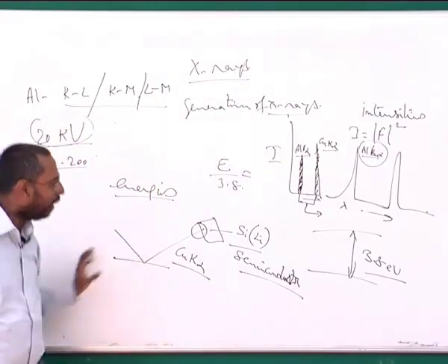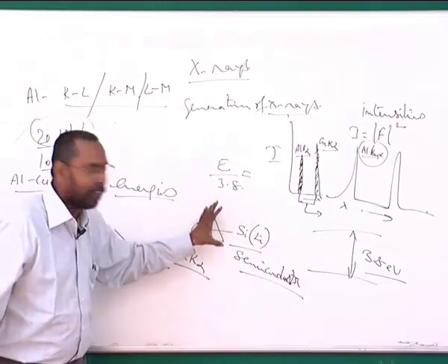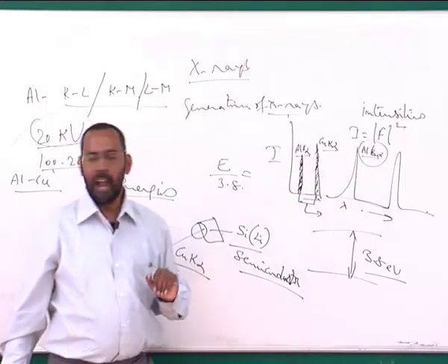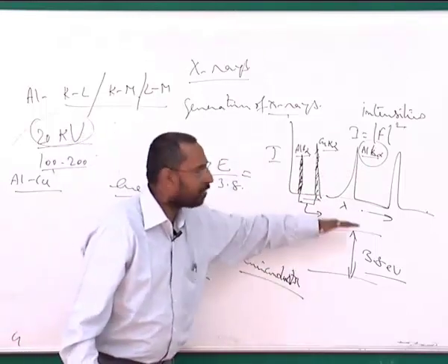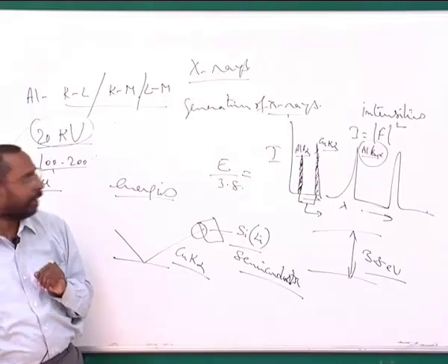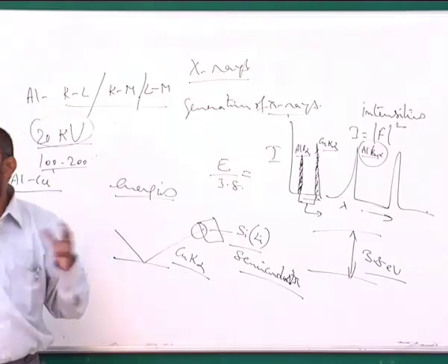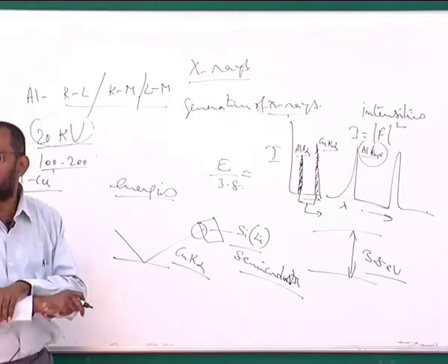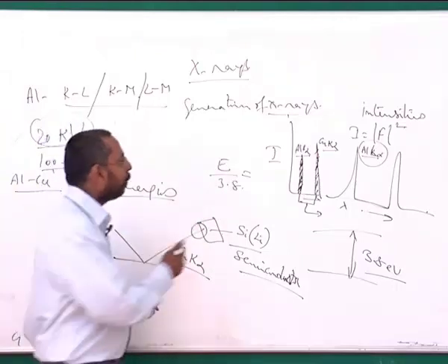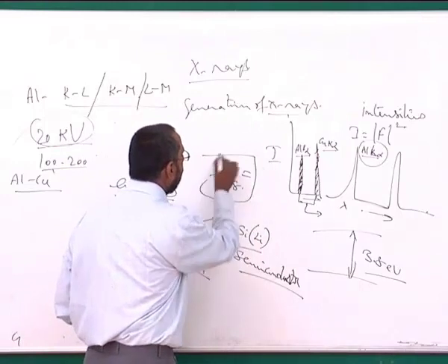Whereas here all the X-rays that are coming out will fall on this, and each of them will excite this, and each of them will generate a certain number of electron hole pairs. And if I can look at how many such electron hole pairs are being generated from each of these, then from that I can find out what is the particular energy that is coming out.